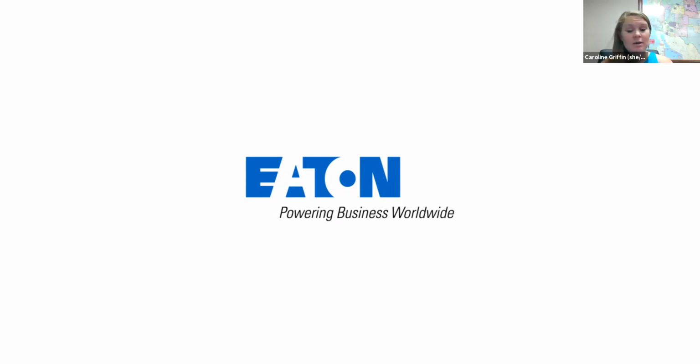A question actually just did come in. Any issues for transportation for supercaps? No, there are no transportation issues. They have their own categorization under the shipping regulations, and there are currently no limitations on that. You do need to be mindful to ship them uncharged in the case of the traditional supercapacitors. And then there's a general requirement to make sure they can't be short-circuited during shipping. So pretty light regulations on them, but you don't have to declare them as hazardous goods or dangerous goods.